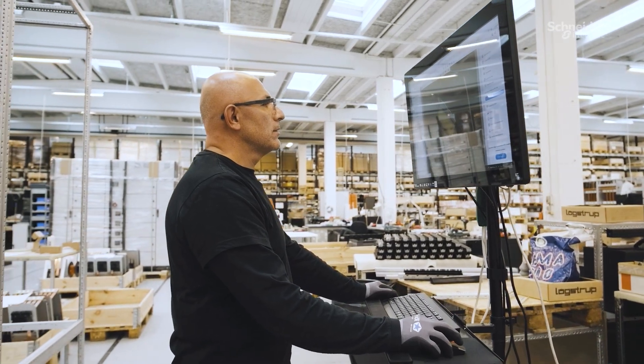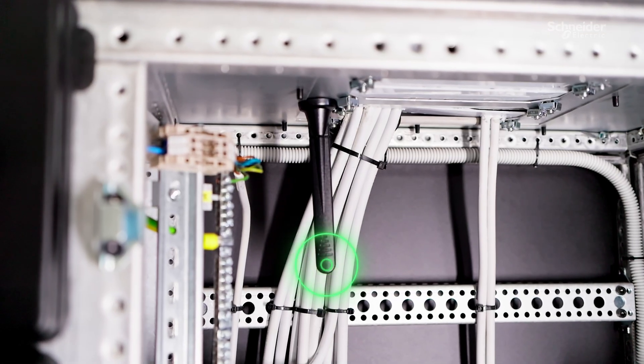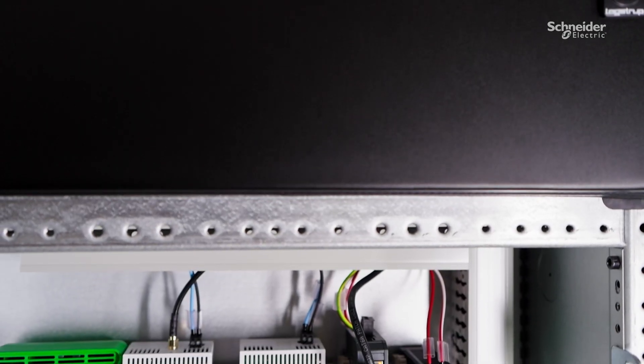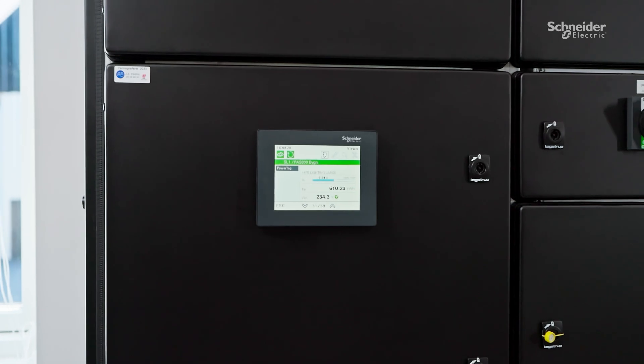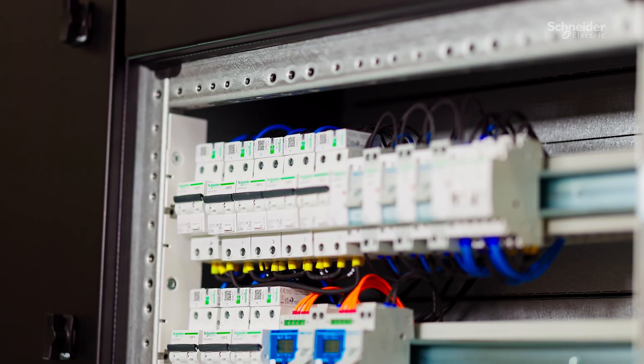The most challenging part with this panel is that it has a lot of enclosed compartments and separations, meaning that the signal has to go through a lot of metallic barriers. We wanted to test the limits of the wireless capability in the panel to ensure that we are confident with the solutions when we recommend them to our customers. Our team of engineers ran multiple tests to test the limits of this type of installation and the wireless connectivity inside these panels.